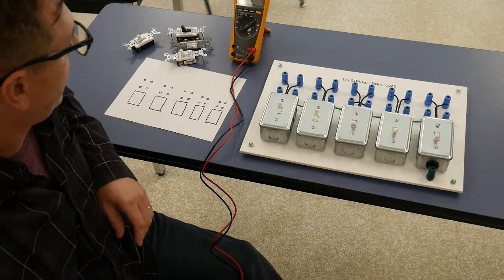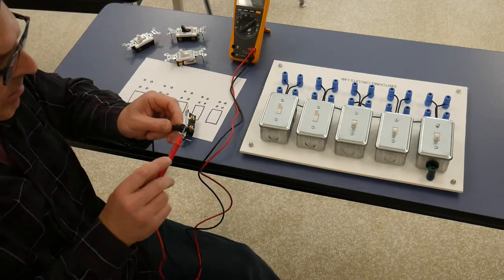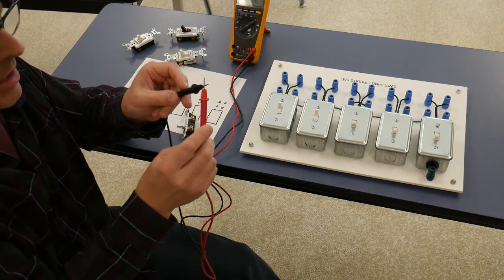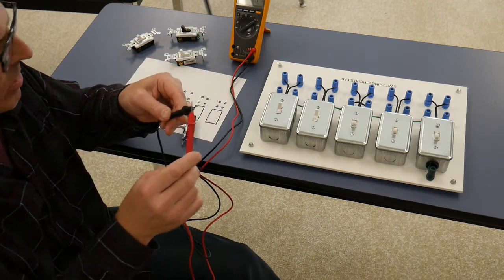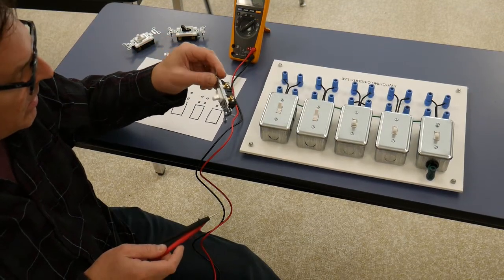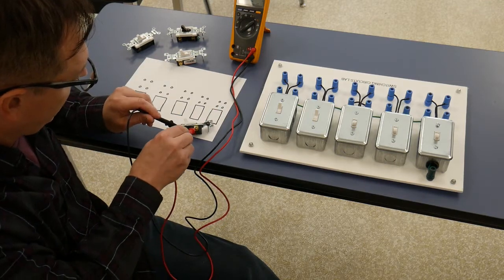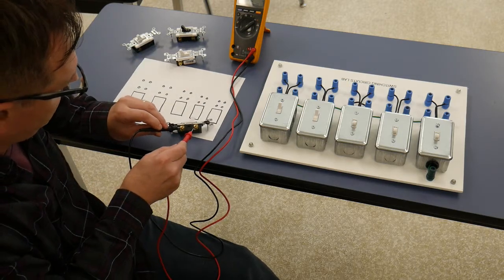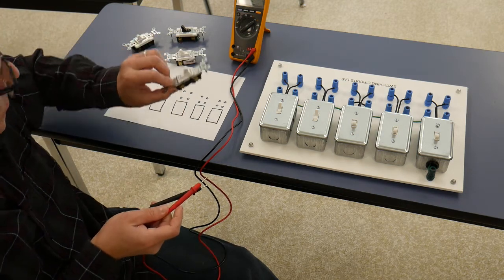Okay, and how do I do that? If I look at just metering a single pole switch, I've got my meter leads on continuity so they beep. If I make a connection, it beeps, so that tells me I have an electric circuit from this lead to that lead. So I have clear continuity. Switches have no resistance or virtually no resistance built into them. So if this switch is in the off position, I should not get any continuity, which I don't. But if I turn that switch into the on position, I should get continuity between these two points, which I do. Okay, so this is a single pole, single throw switch.